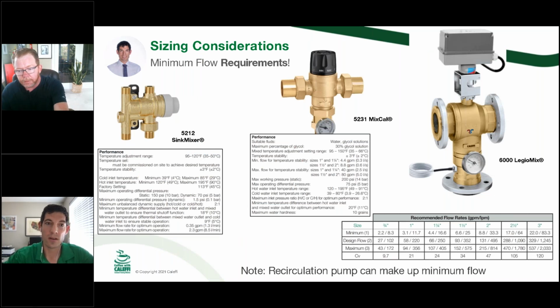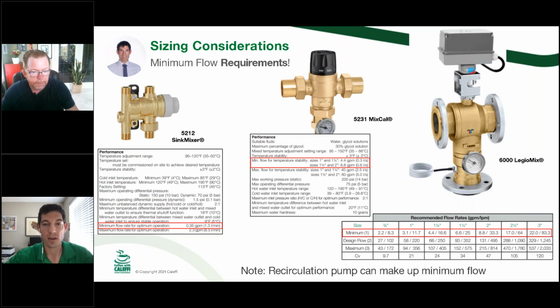All right, so one of the first of many things to look at with a mixing valve is, what is your minimum flow requirement? So let's say you installed that big Legio mix on the right, the flanged 3-inch mixing valve, and you installed it in your house, and then you go down to the sink and you're trying to just have a trickle of warm water to shave. You are going to be so far below the minimum there that it's not going to perform properly. And the reason is the water kind of sneaks past the sensor in the center of that valve that's used to modulate the valve. It's not enough to wash over the entire chamber basically and give you a good accurate reading. So it can hunt a little bit at those really low flow rates.